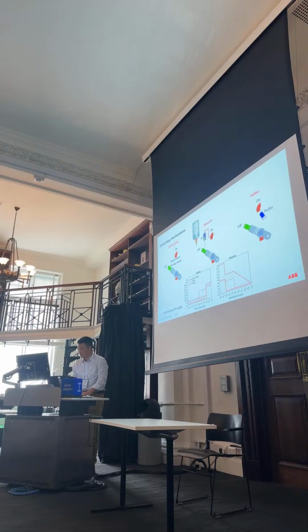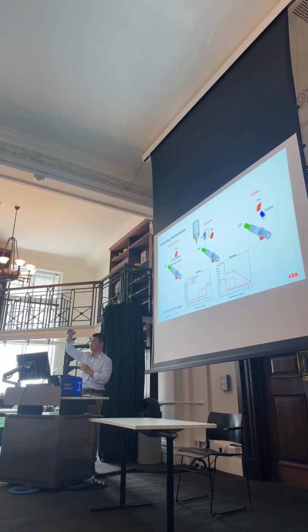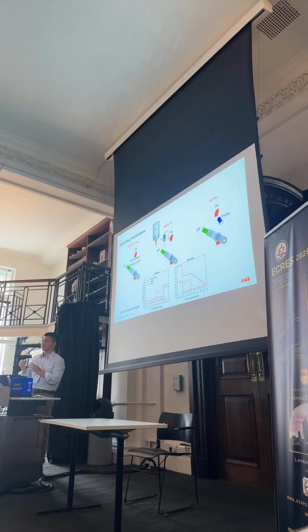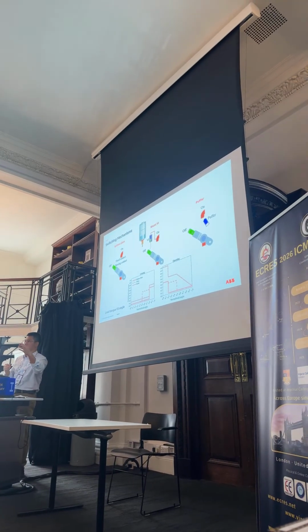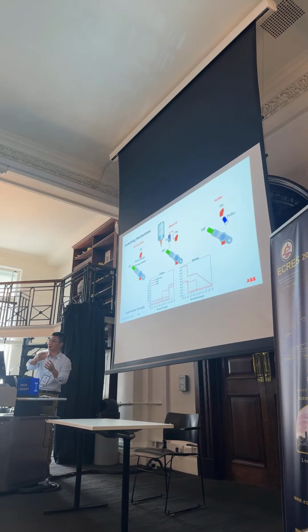After the blade is totally separated from the moving contact, we disconnect again the vacuum interrupter. In this whole process, there is a handover mechanism: we need to hand over the current, first to the vacuum interrupter, then to the fixed contact, as well as for the opening process.